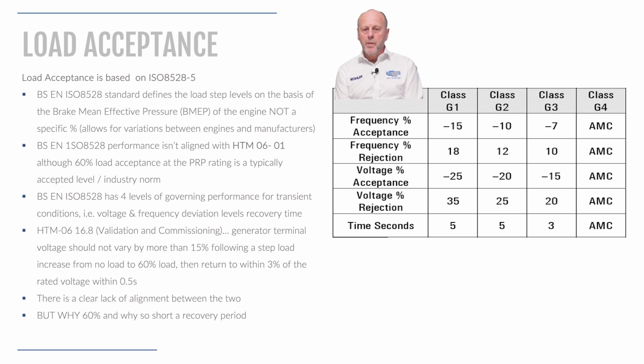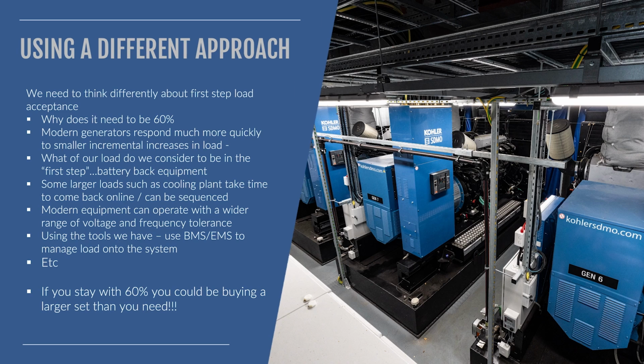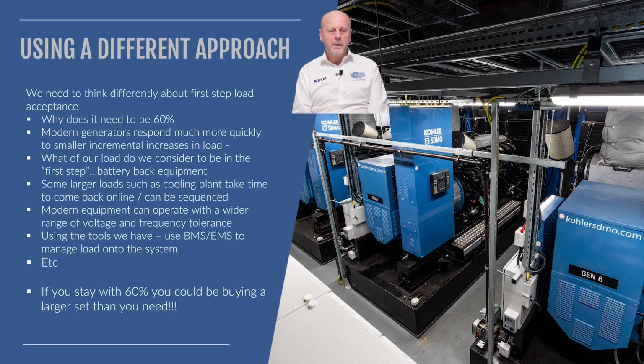So the HTM almost by default effectively sets the bar at 60% G2. This can be achieved in most cases with many sets, but certainly not all, and more so with some of the newer designs. So why 60% and why such a short recovery period? I've entitled this slide using a different approach. So we need to be more open to challenge the 60% load acceptance norm in this new environment. We need to think differently about the first step load acceptance.